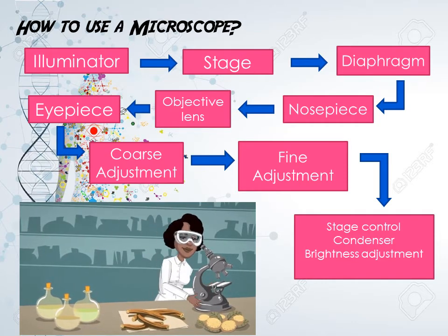After using the microscope, be sure to keep it properly and safely. First, lower the stage using the coarse adjustment. The stage must meet its lowest level, then return the objective to the lowest magnification, which is the scanning objective. Then turn off the switch and unplug the power cord. Then return it to its rightful place.